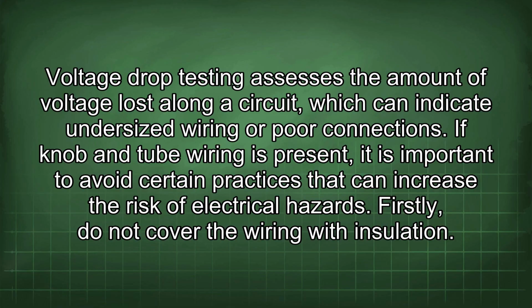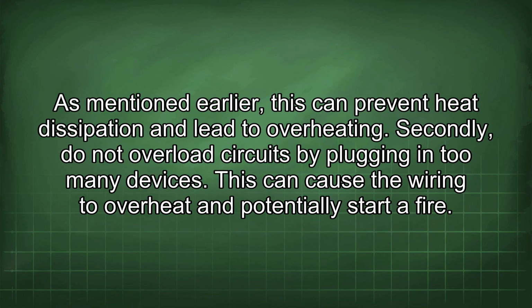If knob and tube wiring is present, it is important to avoid certain practices that can increase the risk of electrical hazards. Firstly, do not cover the wiring with insulation. As mentioned earlier, this can prevent heat dissipation and lead to overheating. Secondly, do not overload circuits by plugging in too many devices. This can cause the wiring to overheat and potentially start a fire.